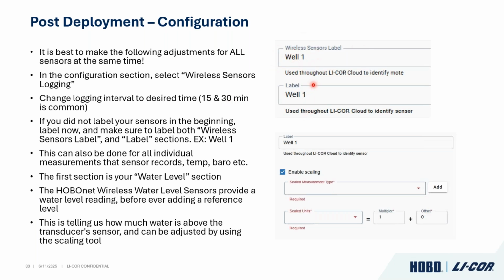And again, both of these sections should be labeled. And also, as you scroll down below the mote, there are different sections. The first section is your water level measurement. Then it's going to be, I think, barometric pressure, and then temperature. You don't really have to touch those other measurements, temperature and barometric. That's all fine. It can be labeled the way it is. If you do want to add a sensor label and identify those as well, you can, but it's not totally necessary. So the next real step is doing your offset and getting an actual reference measurement.